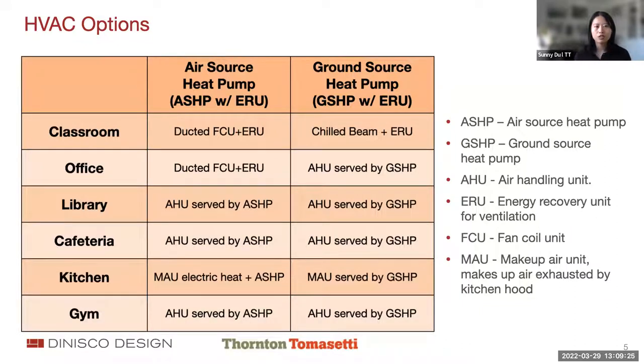So for the two geometries, we also have two HVAC options. One is the air source heat pump. For the air source heat pump, we have ducted fan coil units for classrooms and offices, and an energy recovery unit for ventilation in these spaces. For the rest of the bigger assembly spaces, air source heat pump AHUs are used. For the kitchen, there's a makeup air unit with electric heat backup and an air source heat pump too. Similarly, for the ground source heat pump option, we have active chilled beams for the classrooms and an energy recovery unit for ventilation again, and all other bigger spaces have their dedicated air handling units. With geothermal, the ground source heat pump will provide hot water and chilled water to these units.